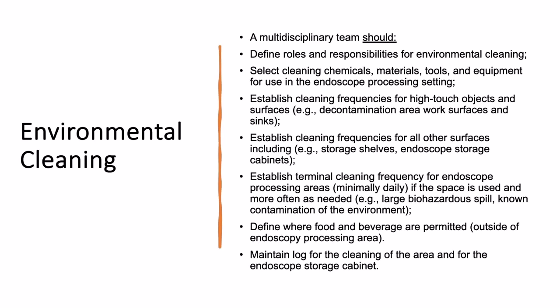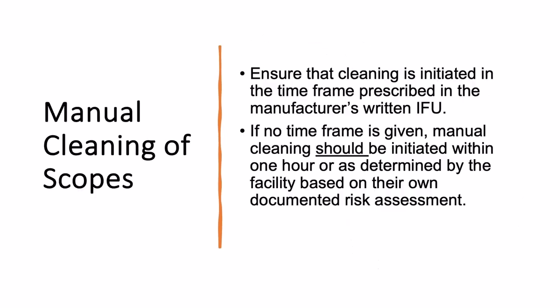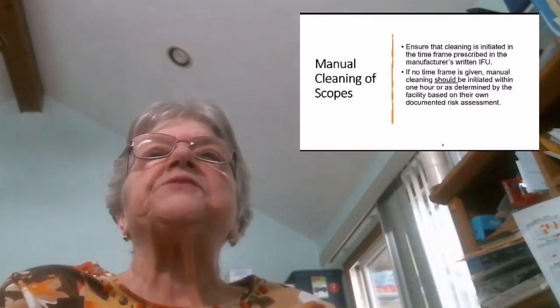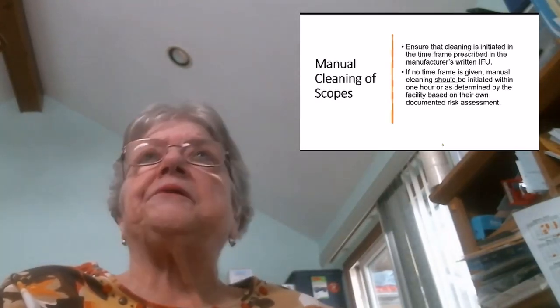So environmental cleaning is very important, and you have to make sure that you're compliant with not only 91, but in your other areas of your department as well. Manual cleaning of scopes. Make sure that cleaning is initiated in the time frame prescribed in the manufacturer's IFU. So the scope manufacturer will tell you how much time between the point of use and the time that cleaning has to be initiated. If they don't give you a time frame, manual cleaning should be started within 1 hour of point of use treatment, or as determined by the facility based on their own documented risk assessment. I would tell you not to wait more than an hour.